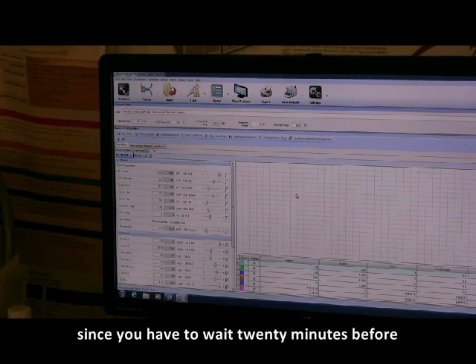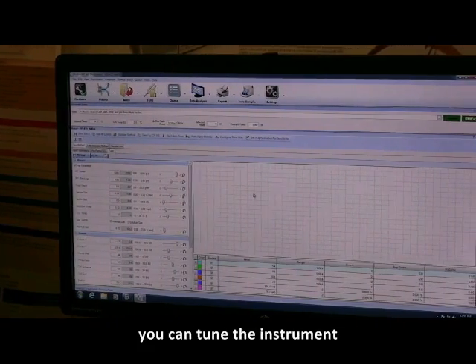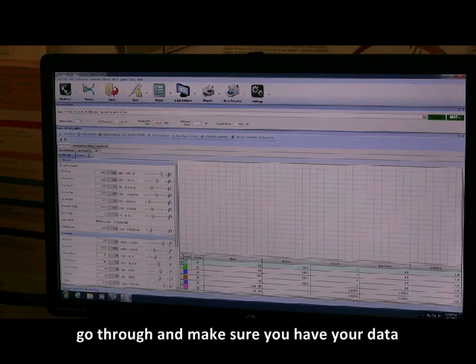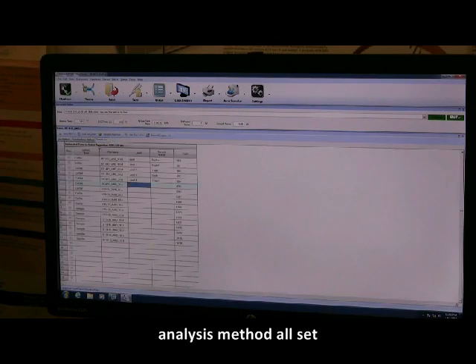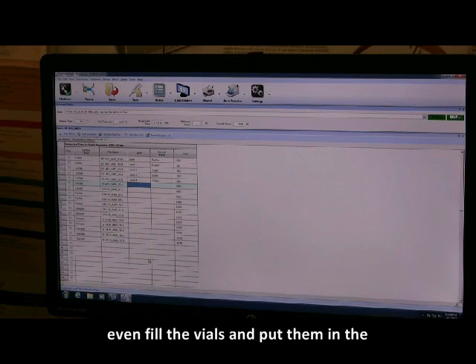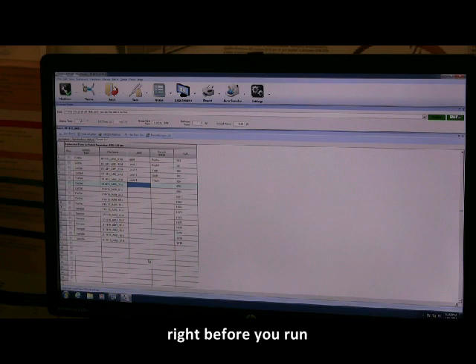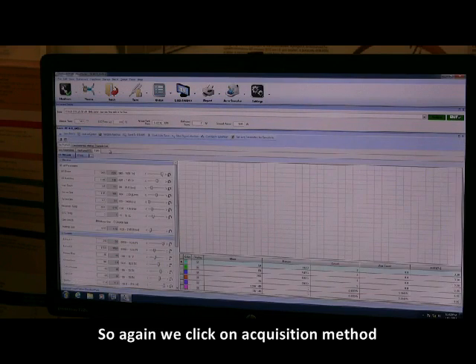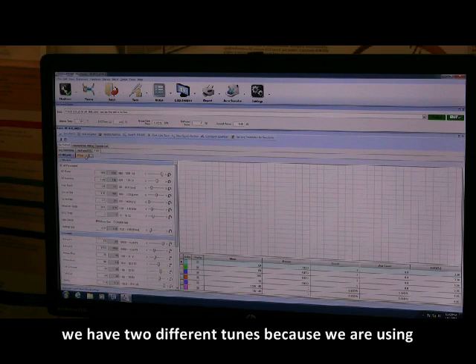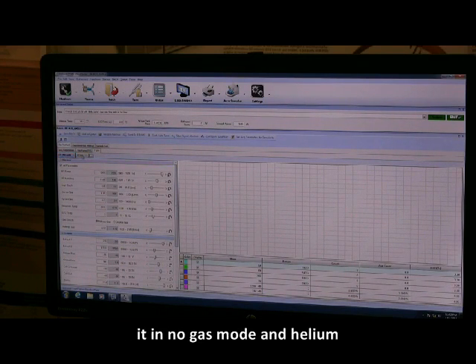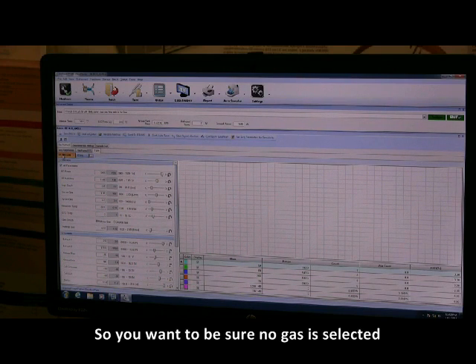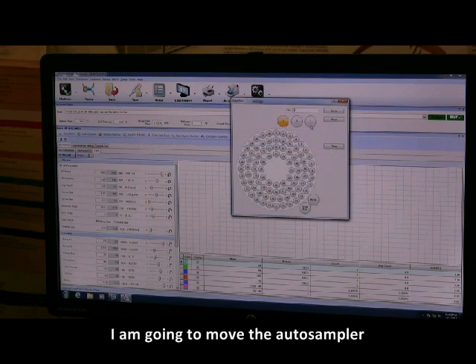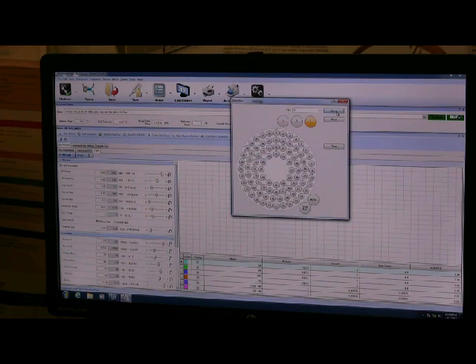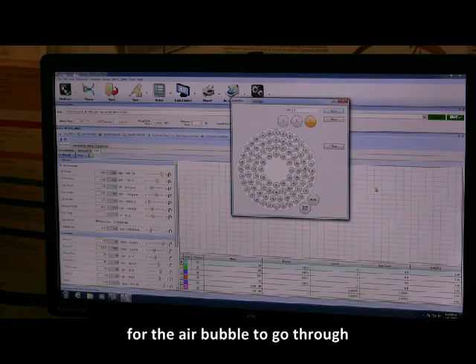So one thing that might be helpful, since you have to wait 20 minutes before you tune the instrument, you can turn on the instrument, then go through and make sure you have your data analysis method all set, make your whole sample list, maybe even fill the vials and put them in the auto sampler, and then tune right before you run. So again, we click on Acquisition Method, Tune. You'll see here we have 2 different tunes because we're using it in no gas mode and helium mode. So you want to be sure no gas is selected. I'm going to move the auto sampler to vial 3, which is my tune solution. And again, I'm going to wait for the air bubble to go through and then wait an additional 20 seconds for it to stabilize.